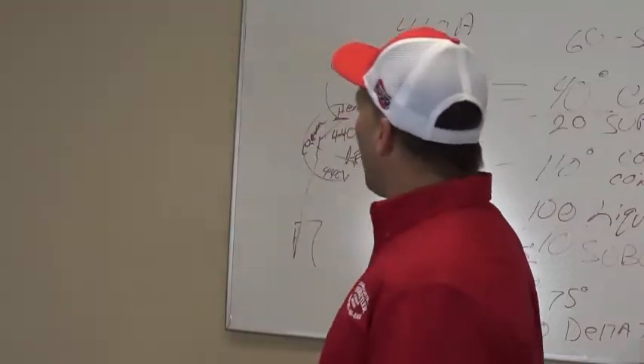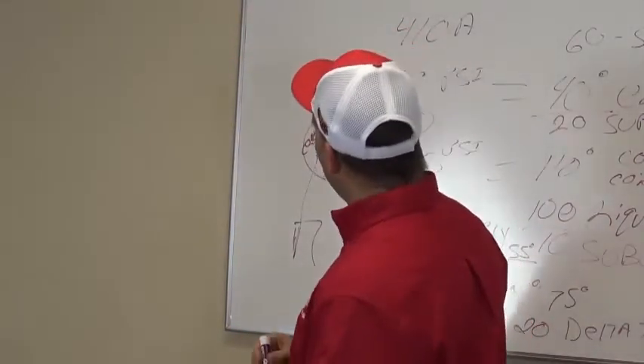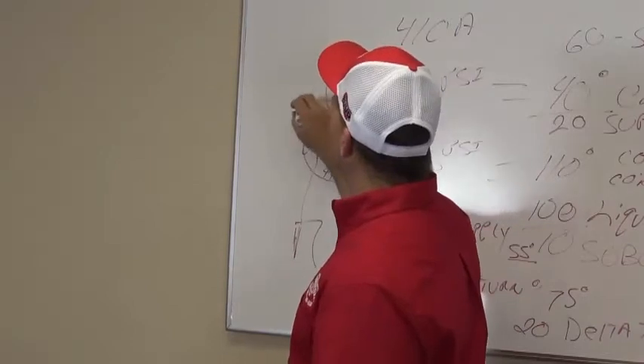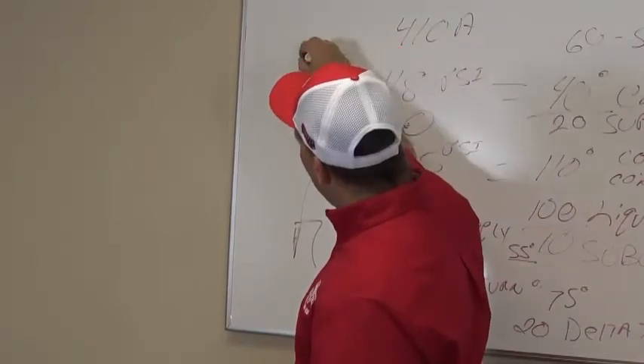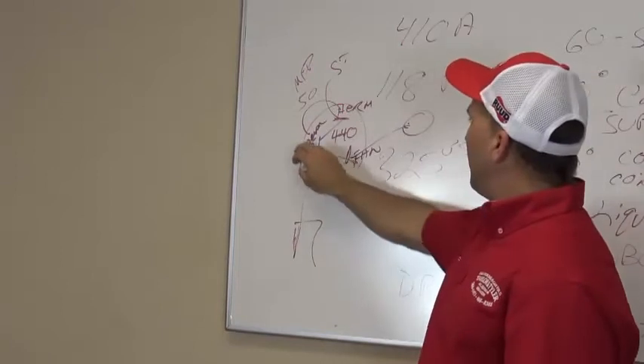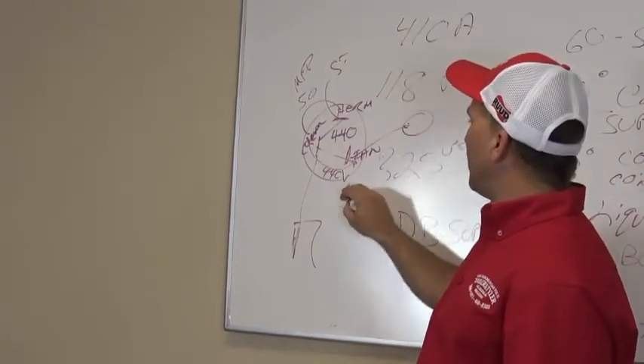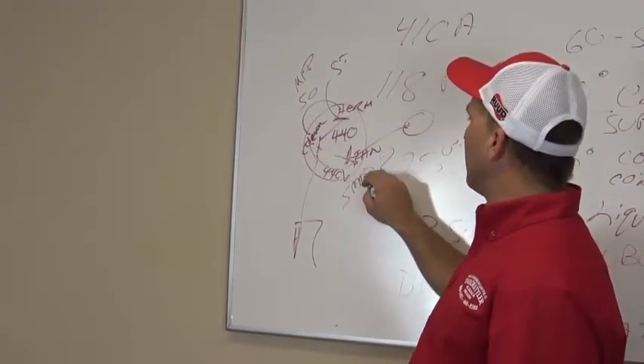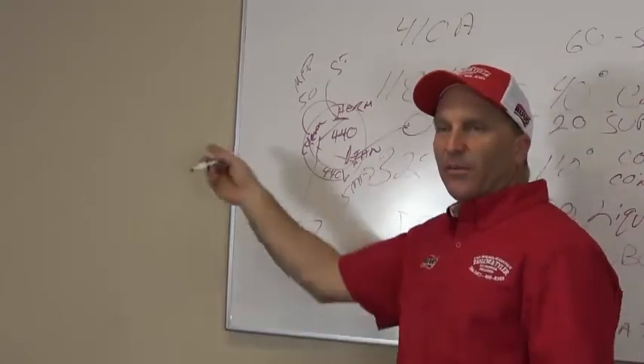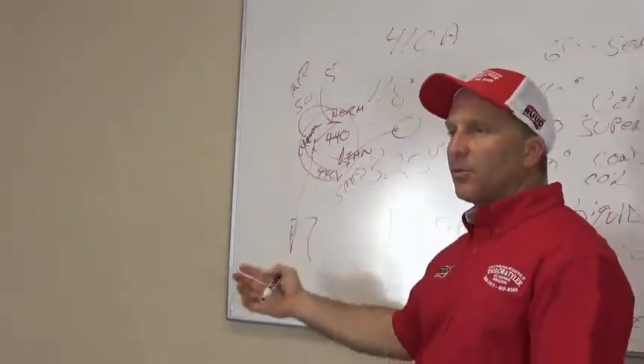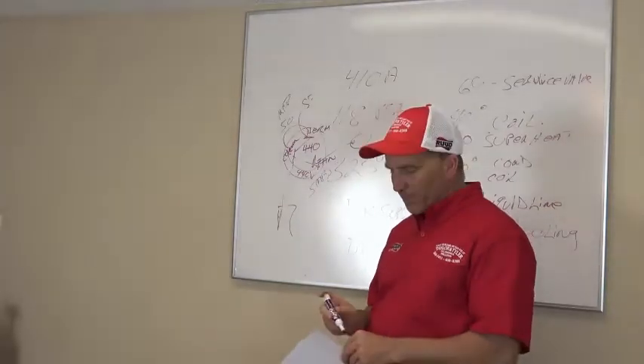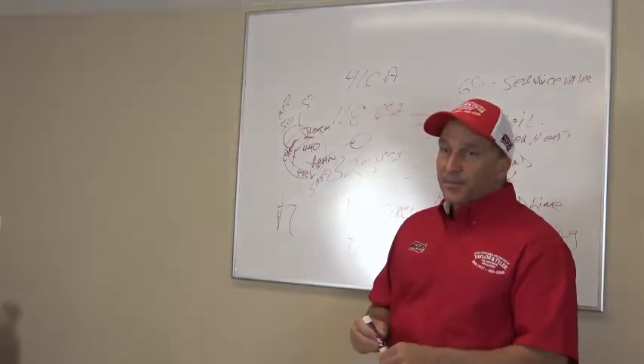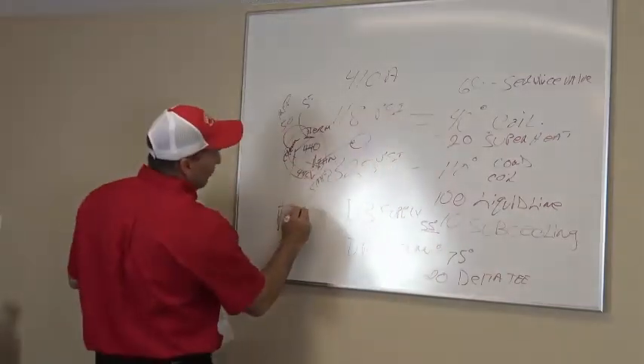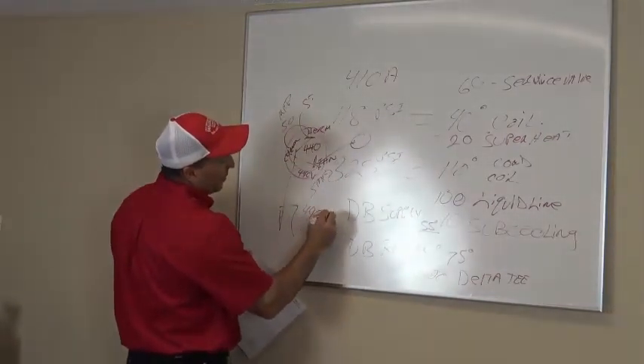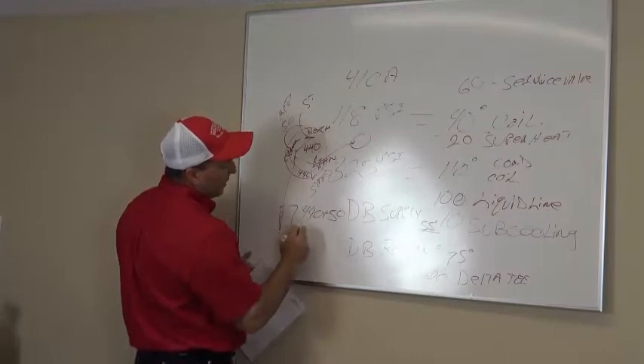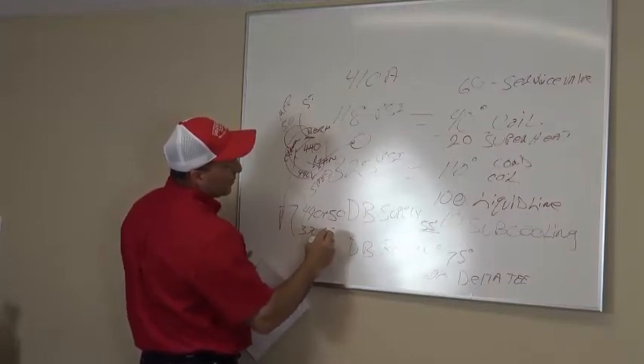The 50 microfarads is between here and here. So between this one and this one, it reads 50 MFD. Between this one and this one, your fan, it reads 5 MFD. Now, it may be a 50 plus 10, a 50 plus 7.5, a 50 plus 12.5. Okay? Now, here's another thing. You can have a 440 plus 50. You can have a 370 plus 50.